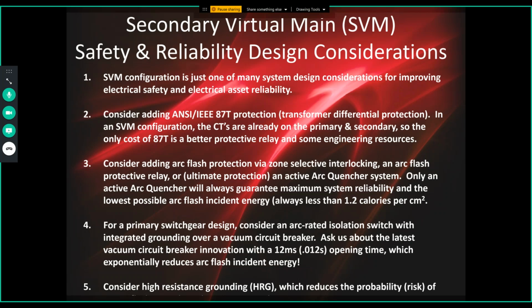The next thing we would point out is, if you're going to implement a secondary virtual main, I would argue even for smaller transformers below 5 MVA in size, since you already have both CTs there and you have a protective relay, spend the few hundred extra dollars necessary to get a better protective relay which incorporates transformer differential protection. So now we're not only reducing arc flash incident energy in the secondary switchgear, we're reducing arc flash incident energy and protecting the transformer itself. 87T, there is no better solution than differential protection.